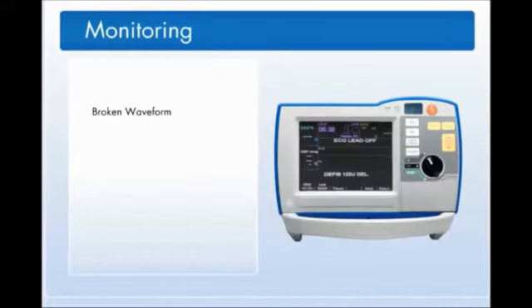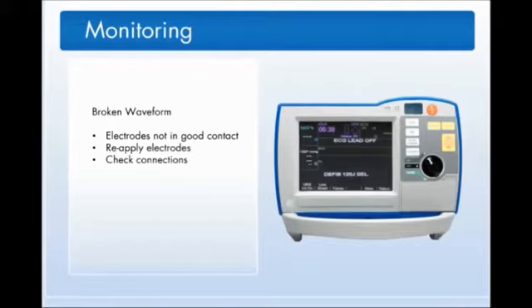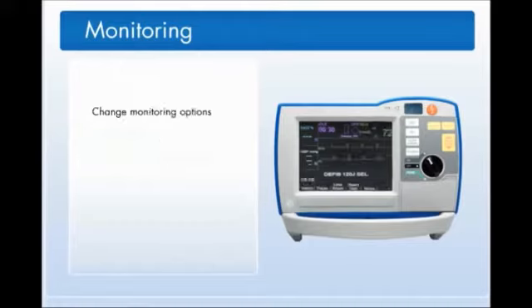If, while monitoring your patient, you see a broken line on the defibrillator display screen, it is an indication that the electrodes are not in good contact with your patient's skin. Reapply the electrodes and check the connections between the electrodes and their cables. You will hear a beep that will sound with each heartbeat.